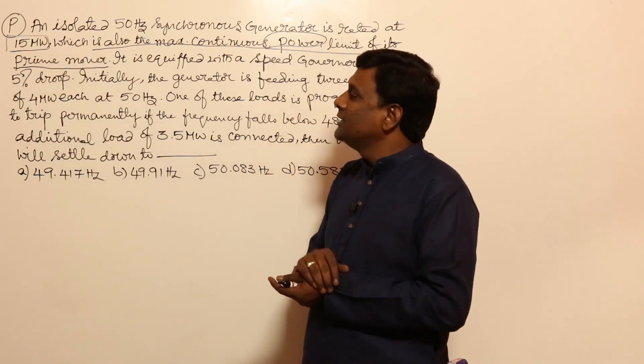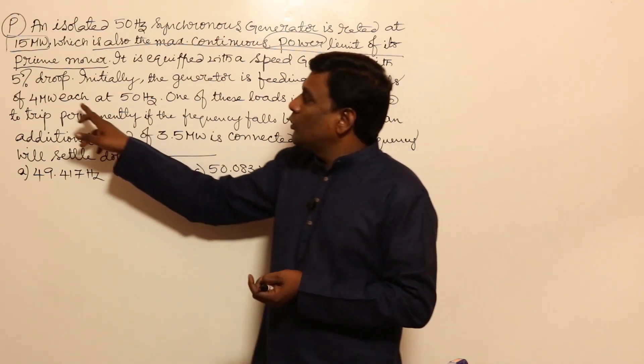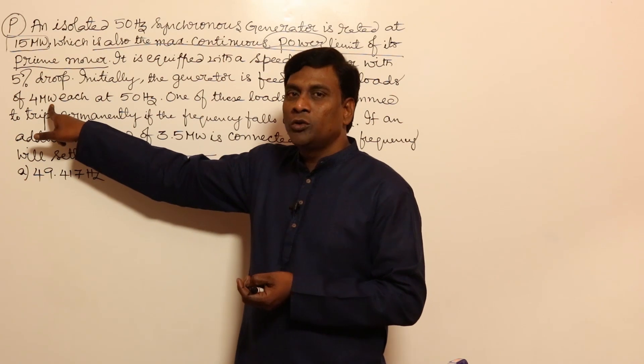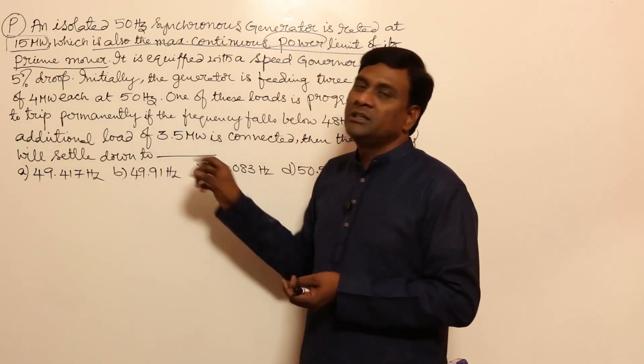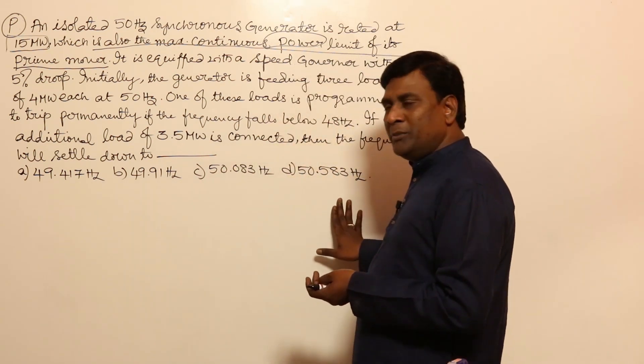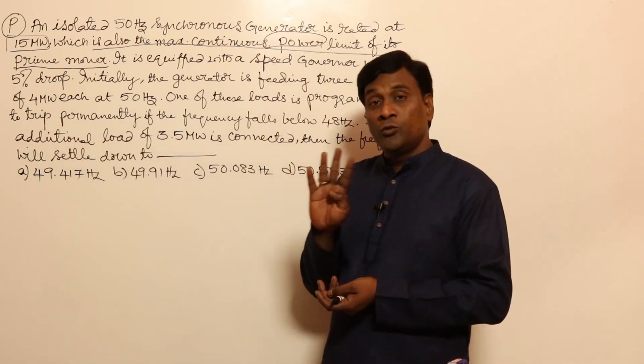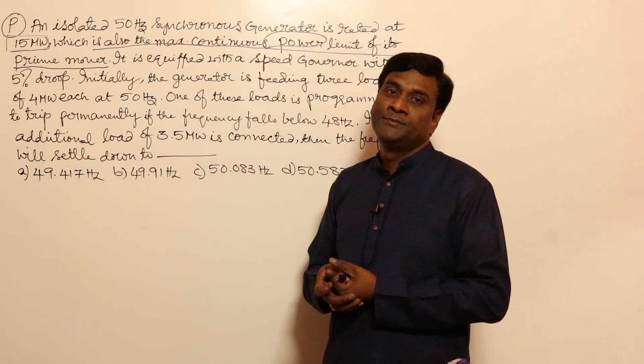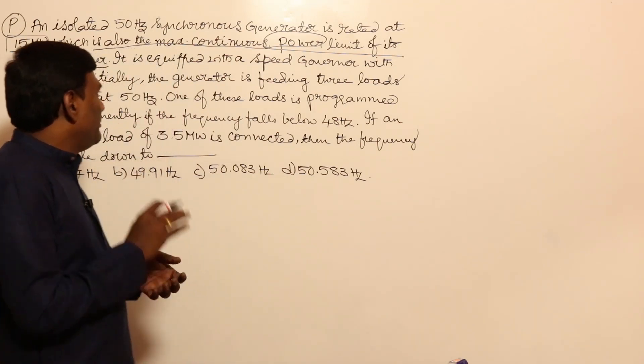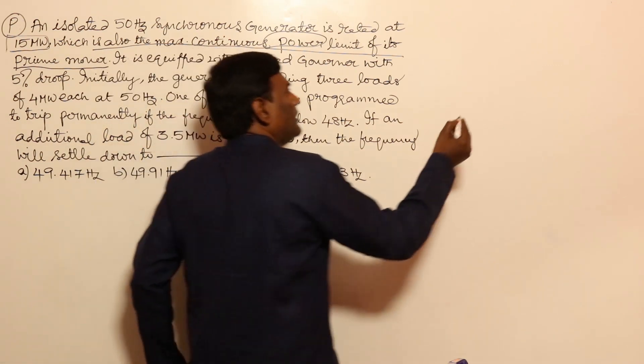This is contradictory. If any answer were less than 48 Hz, one four-megawatt load would trip, leaving two loads: 2×4 + 3.5 = 11.5 megawatt. But since the given options do not include anything less than 48 Hz, all three loads remain connected — 12 + 3.5 megawatt. The key keyword in this problem needs to be identified.